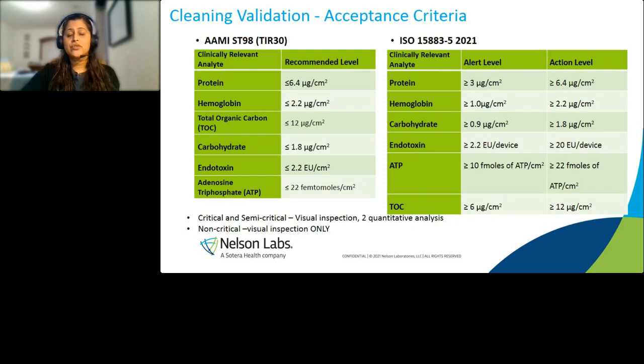We do have acceptance criteria that we have to meet per standards. If they don't meet these acceptance criteria, you fail the device and you have to increase your cleaning procedure to meet the acceptance criteria. Nobody's going to go redesign because you're at the end of your phase when they're doing these validations. Often we see people just increase the procedure. So when you see long procedures for cleaning validation, it's because we didn't meet these acceptance criteria for ISO and AAMI. And that's what makes them longer. We have to add now more flushing or more rinsing or ultrasonic cleaning steps to meet these. So there is a criteria for them and we have to meet them.